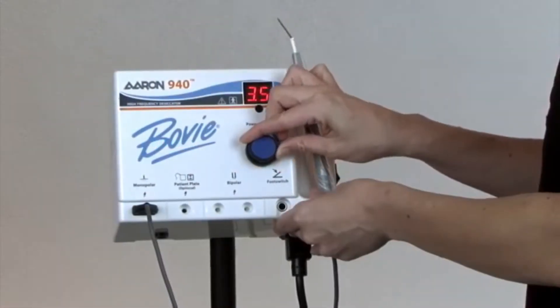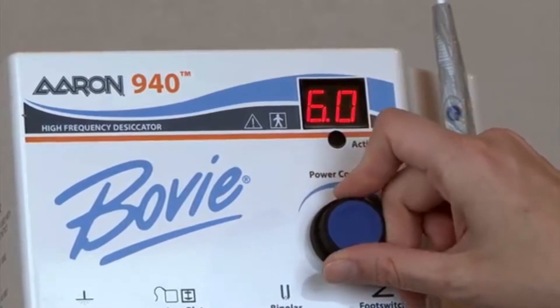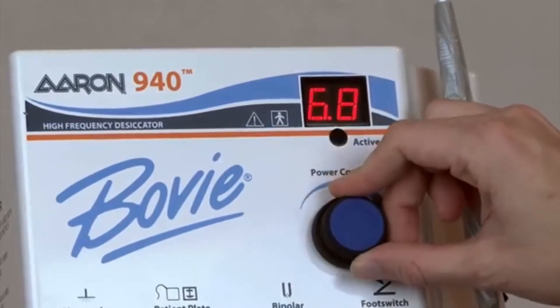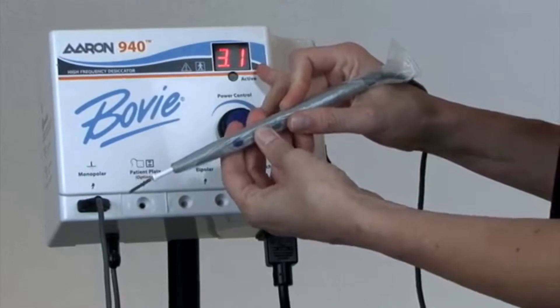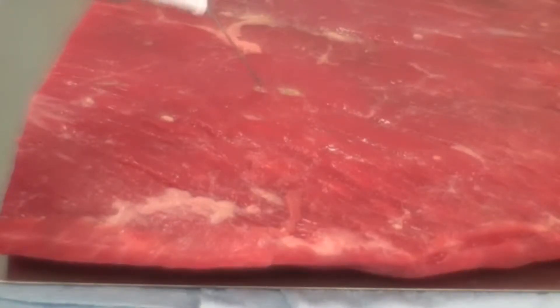It is important to always begin with a low power setting. When you need to increase the power output, rotate the power dial clockwise or push the up power button on the handpiece. The best way to get comfortable with the Aaron 940 is to practice with a raw, lean flank steak. This allows you to get comfortable with the various power settings and the different effects of each tip.